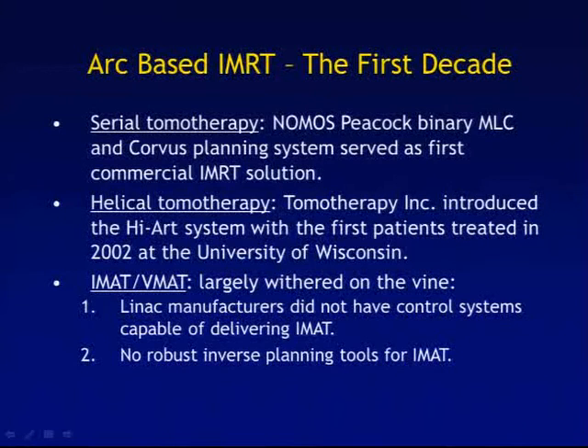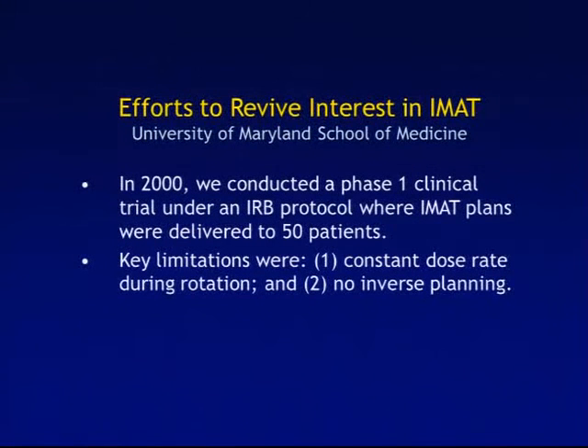During the time that IMAT was languishing, ongoing research was happening. At the University of Maryland working with Cedric Yu, we did a Phase I clinical trial under IRB protocol where we treated 50 patients with IMAT. But we had key limitations: the linear accelerator couldn't vary the dose rate, so we had a constant dose rate during rotation, and there was no robust inverse planning tool. So this was sort of IMAT lite.